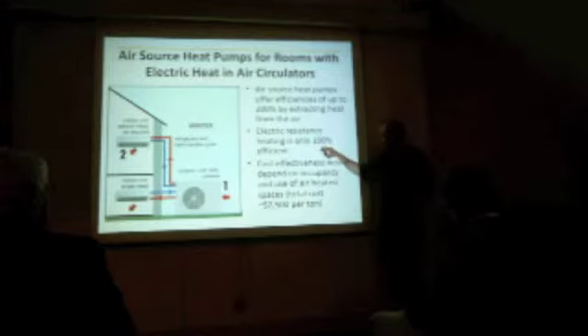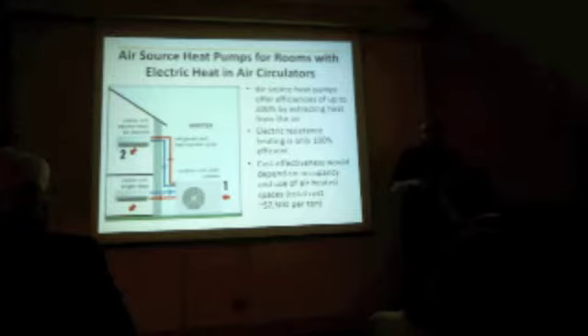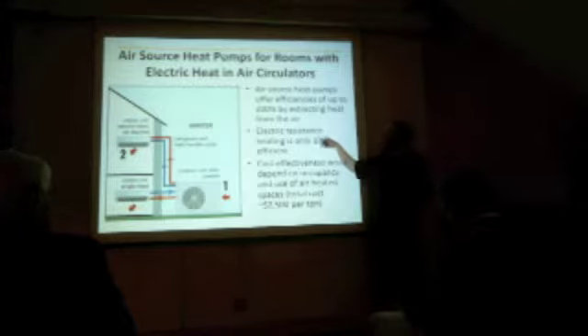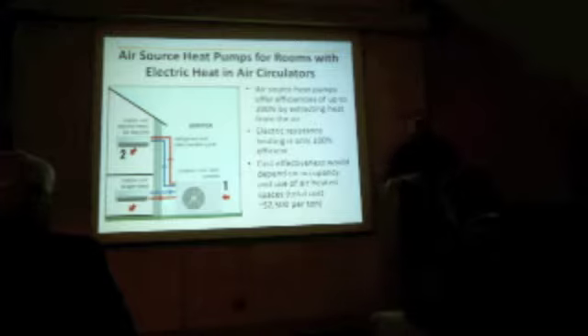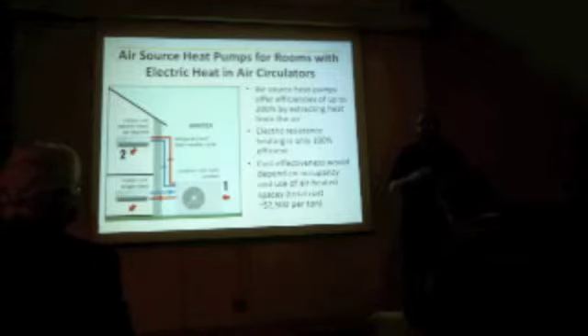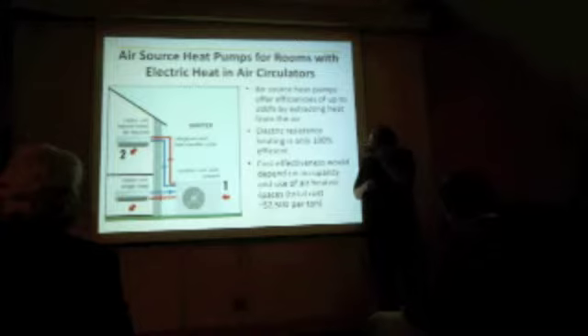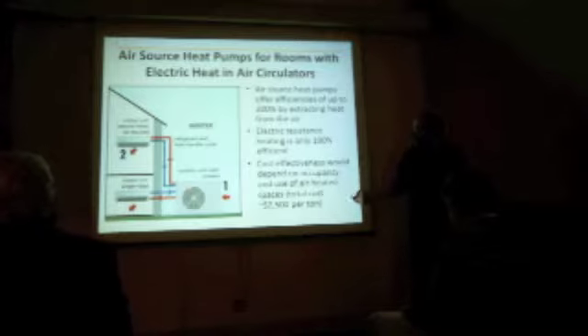And one thing that you have is a couple of spaces that are right now using just pure electric resistance heating, which is the air handlers here. If those were instead using a heat pump, you would cut the energy used to heat and cool these kinds of spaces by about a factor of 2. Of course, the cost effectiveness depends on how often these few spaces are actually used, and how much they're used in winter versus summer. The typical cost for one of these systems is about $2,500 per ton. The ton is your standard heating unit, like your furnace or boiler at home. So you have a couple of spaces that might be particularly good because you're already using electricity to heat, and you're using it in a less efficient way. And so the cost reductions for heating the space might be able to pay those back.